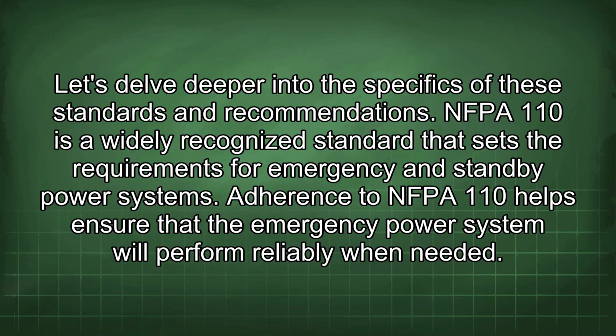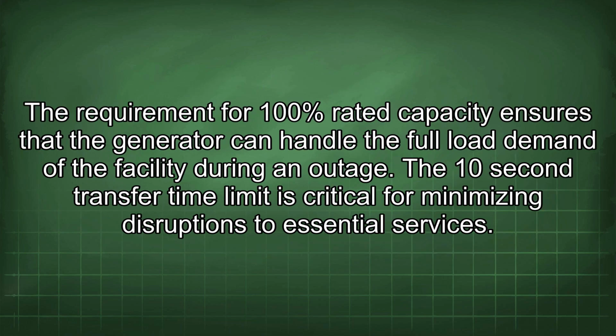NFPA 110 is a widely recognized standard that sets the requirements for emergency and standby power systems. Adherence to NFPA 110 helps ensure that the emergency power system will perform reliably when needed. The requirement for 100% rated capacity ensures that the generator can handle the full load demand of the facility during an outage. The 10-second transfer time limit is critical for minimizing disruptions to essential services.